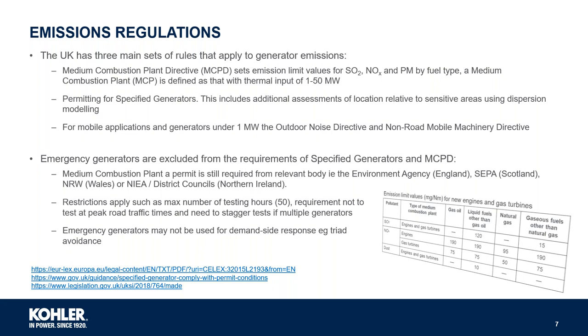However, a permit is still required from the relevant body: the Environment Agency in England, SEPA in Scotland, NRW in Wales, and NIEA for Northern Ireland. This is to ensure they're operated as standby machines, so restrictions are applied, such as limiting test hours to 50 hours a year. Generators cannot be tested during peak times, and tests need to be staggered if multiple generators are installed on site. Emergency generators may not be used for demand side response, such as triad avoidance. However, in the event of a power outage, they can operate for an unlimited number of hours.